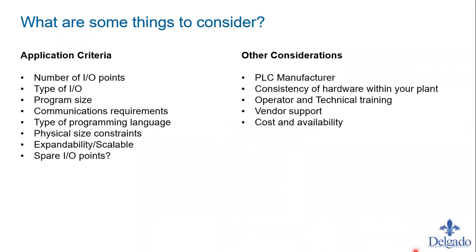What are the criteria to consider? You have to know the number of I/O points in your system. You have to get a drawing, have someone tell you, or physically count — knowing how many analog or discrete push buttons, switches, and transmitters are out there so you can get a complete count of what you have to wire in your PLC. The type of I/O — discrete or analog — makes a difference. The program size is also a factor; the number of I/O points often helps determine the program size.